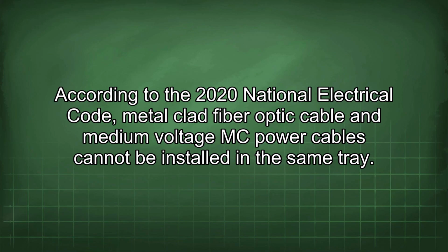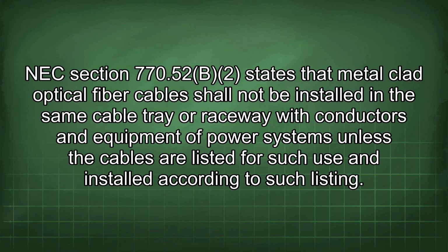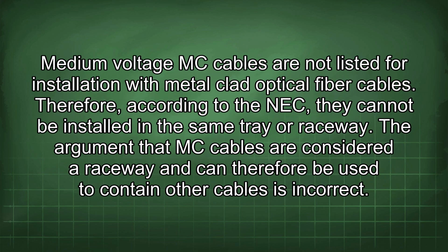According to the 2020 National Electrical Code, metal-clad fiber optic cable and medium-voltage MC power cables cannot be installed in the same tray. NEC Section 770.52(B)(2) states that metal-clad optical fiber cables shall not be installed in the same cable tray or raceway with conductors and equipment of power systems unless the cables are listed for such use and installed according to such listing. Medium-voltage MC cables are not listed for installation with metal-clad optical fiber cables. Therefore, according to the NEC, they cannot be installed in the same tray or raceway.